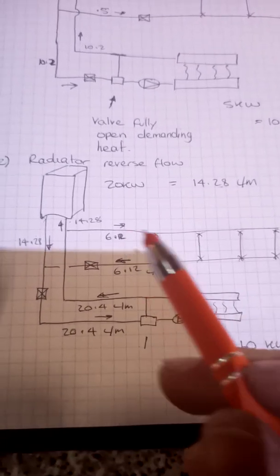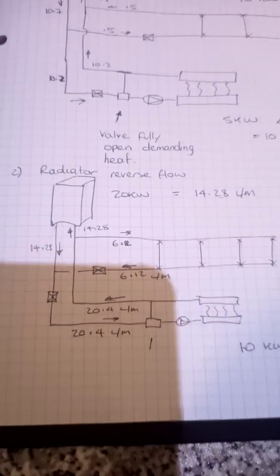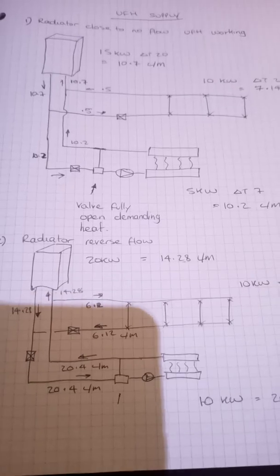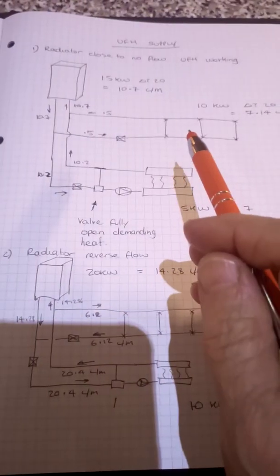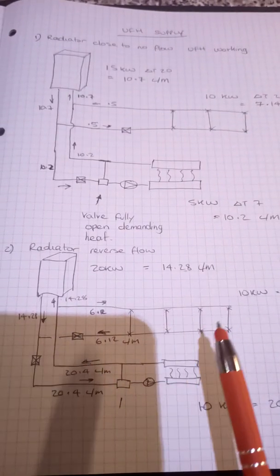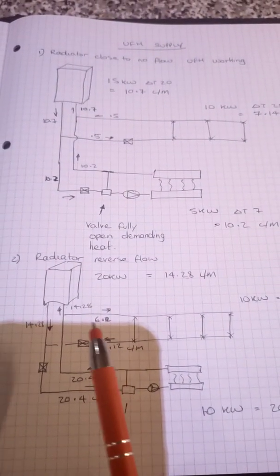So here we can see we've actually got a reverse flow in the radiators, and this is something I come across quite regularly in the winter time under high load conditions when I'm fault finding, when I get called out to radiators not working. Here you'd have some heat in the radiators, I guess, because you'd be getting flow rate through of the return temperature from the underfloor heating.